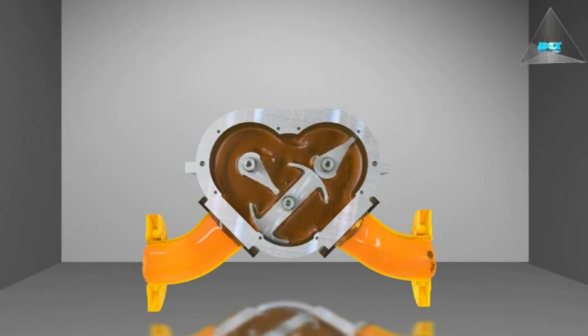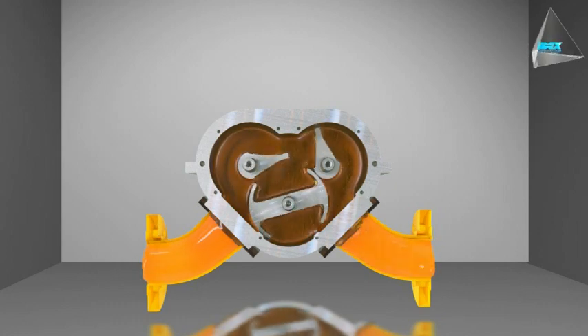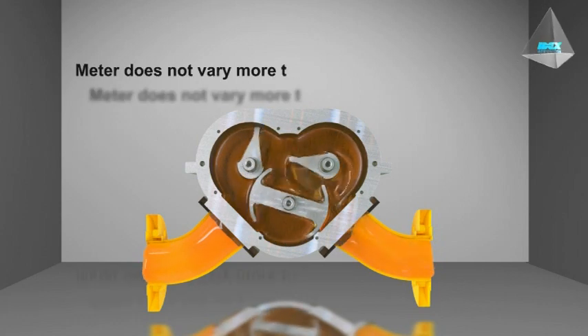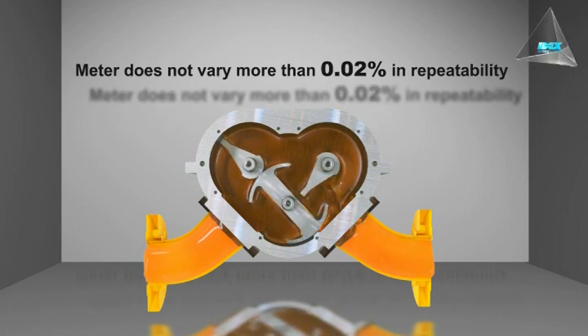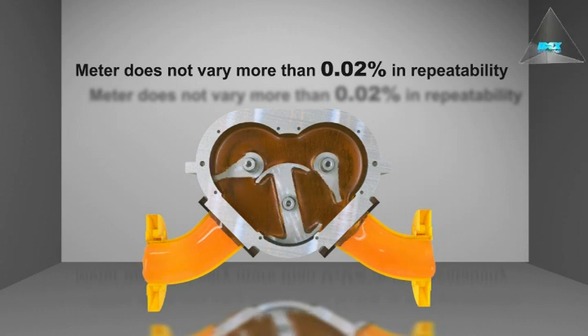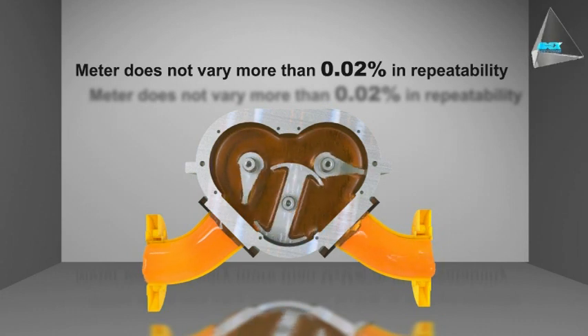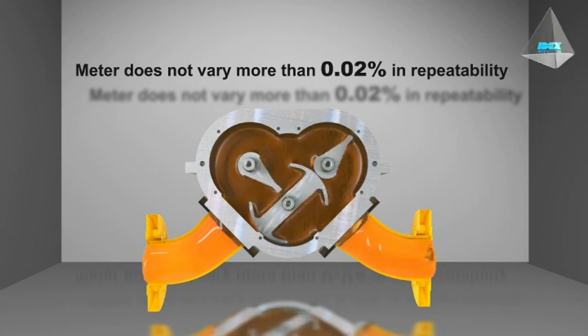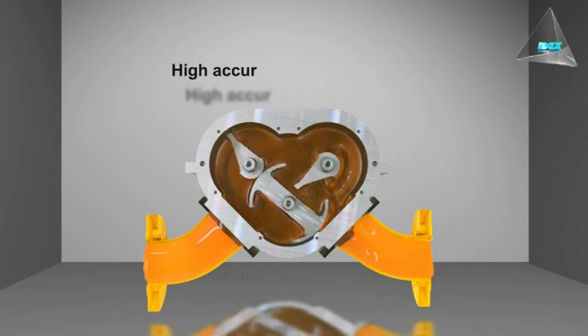With all other conditions being constant, the LC meter does not vary more than 0.02% in repeatability over the entire range of flow and has a very high accuracy of plus or minus 0.05%. There is no metal-to-metal contact within the metering element.